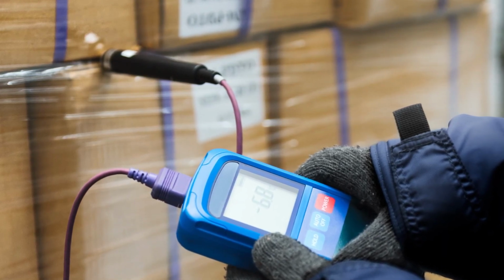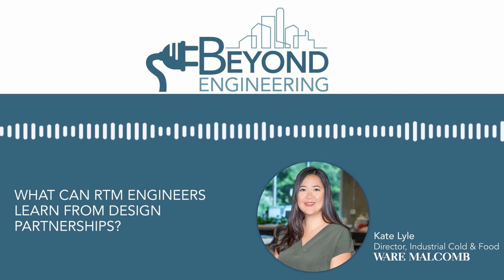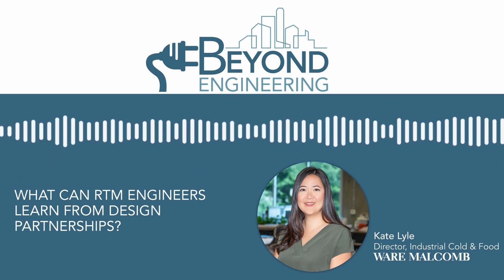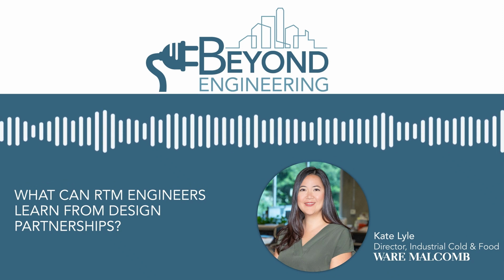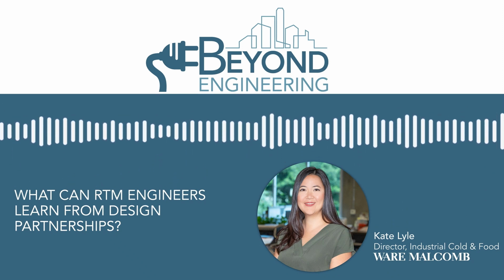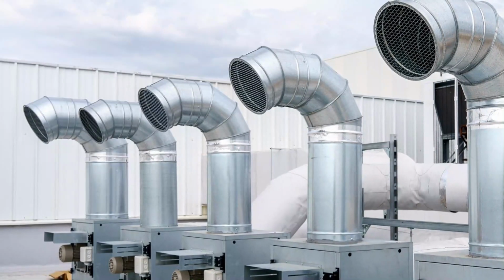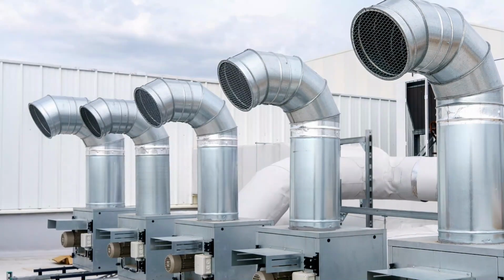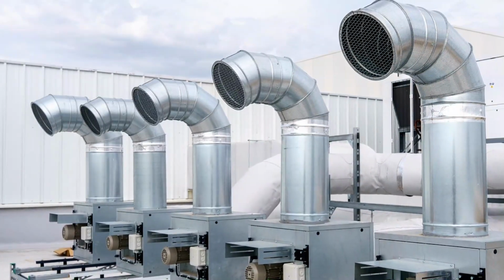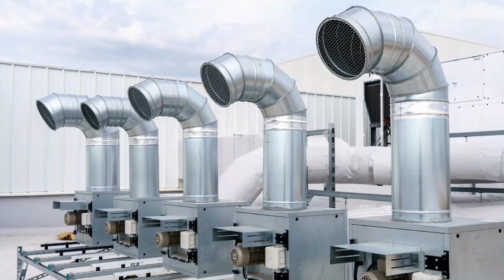Some of the demising issues come when you have multiple tenants in a speculative building, right? Absolutely. It can be really challenging because not only are you trying to keep the two tenants separated from a security standpoint and from a usage standpoint, but you're also having to deal with things like, oh gosh, I've got a really cold tenant here. I've got a really warm tenant here. We have to make sure that there isn't any thermal transfer and that we're not ending up with water on tenant A's floor because there's too much moisture coming from tenant B's refrigeration design too. It's not like an HVAC system where you have a lot of little units. A lot of times these refrigeration units are covering tens of thousands of square feet. So you have to think, okay, am I doing a design that's going to have lots of little spaces, which is more units, which is more costly, or am I doing a design that has fewer units but won't be able to be demised in the same way?